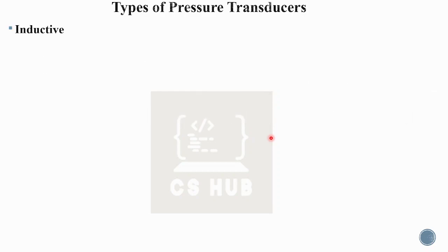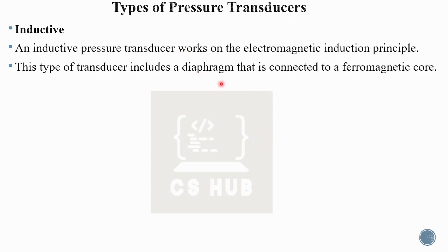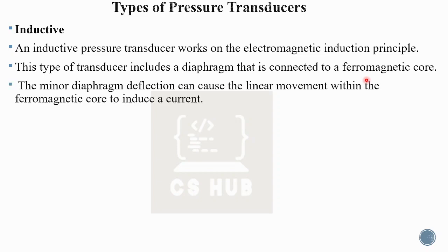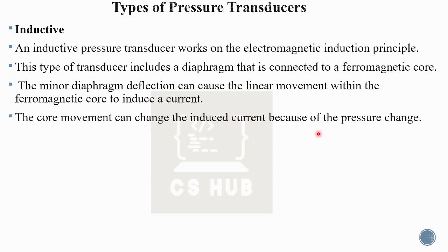The inductive transducer works on the electromagnetic induction principle. The diaphragm is connected to a ferromagnetic core. A minor diaphragm deflection causes linear movement of the ferromagnetic core, inducing a current. The change in the diaphragm causes a change in the ferromagnetic core, resulting in a change in flux and a change in current. The core movement changes the induced current because of the pressure change, and the change in current can be converted to a utilizable signal.